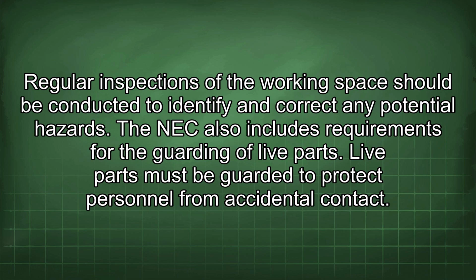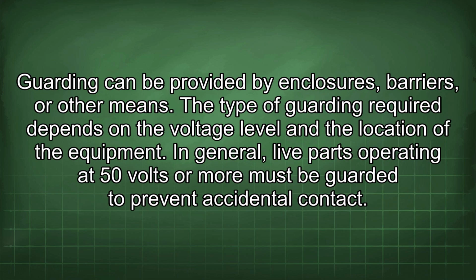The NEC also includes requirements for the guarding of live parts. Live parts must be guarded to protect personnel from accidental contact. Guarding can be provided by enclosures, barriers, or other means. The type of guarding required depends on the voltage level and the location of the equipment. In general, live parts operating at 50 volts or more must be guarded to prevent accidental contact.